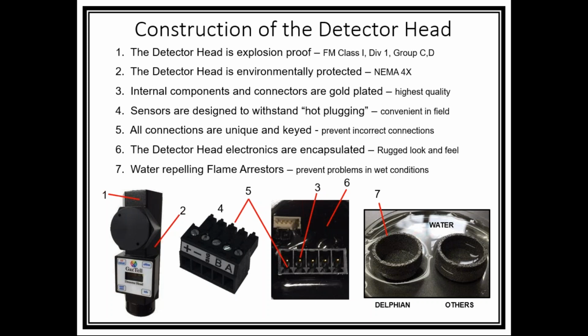Number 6, the detector head electronics are encapsulated. This is one of the more important features that we have on the GasTel, and in fact, Delphian has always been a big believer in encapsulation. If you're familiar with the 550 system and determinator, all the electronics are potted, which is encapsulation. The environment can no longer get to a board level component because they are encapsulated in a black epoxy that prevents the elements from getting to the electrical parts of the PC board.